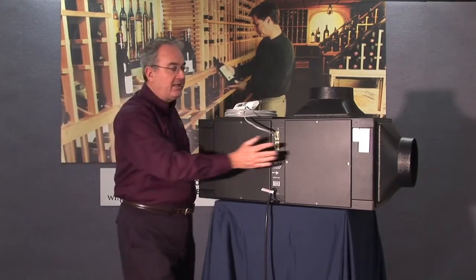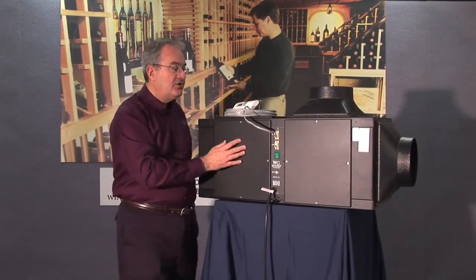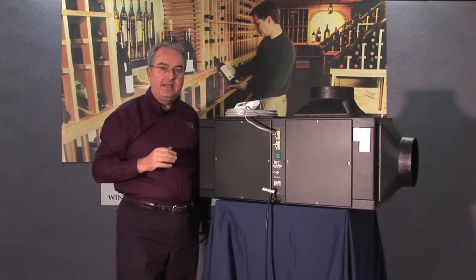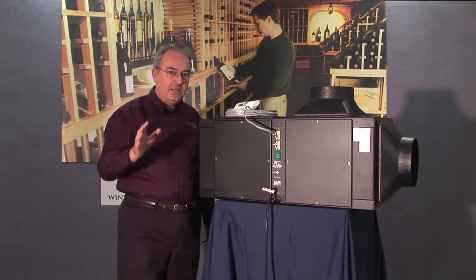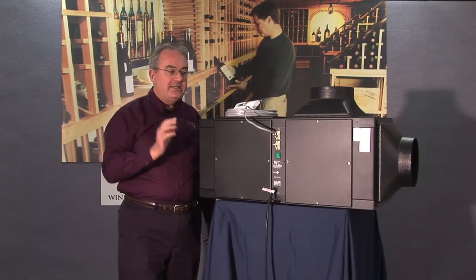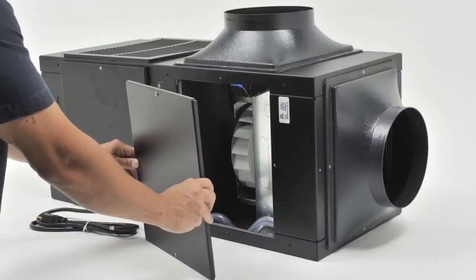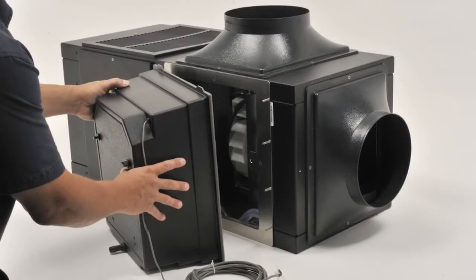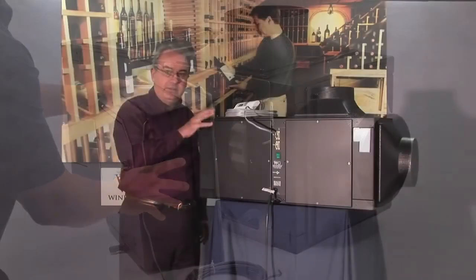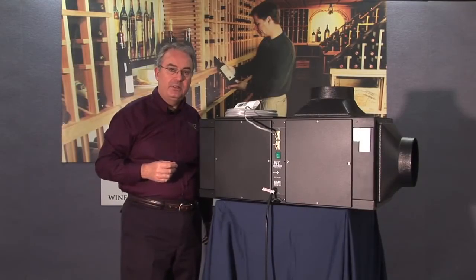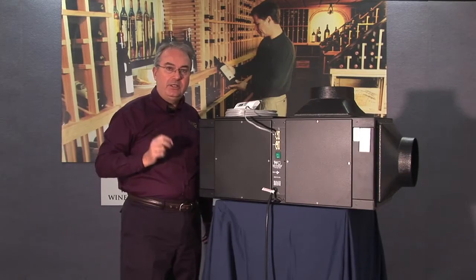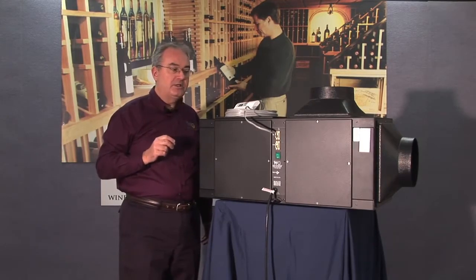But you'll notice these panels. We have panels on both sides of the units as well as on the top, and that allows you to actually use more ducts if you'd like to. These same panels can also be used to mount our optional humidifier. So the humidifier is actually integrated with this unit when it's used, and in one piece of equipment you are genuinely controlling humidity as well as temperature.